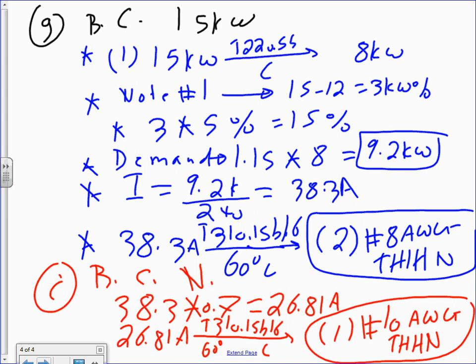That's interpreting. If you read through, it says, if your ranges are larger than 12, then anything larger than 12, increase the demand 5% for every kW more than 12.